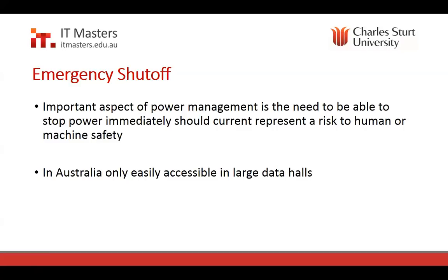So if you ever are going to hit it, don't hit it accidentally, like an old boss of mine did, wheeling in a trolley full of equipment, and he accidentally bumped into the emergency shut off for the data hall. So that was a good start to his day. What a disaster. Yes, he was actually a field tech for Honeywell at the time, and he got called out to one of the Telstra data centres in Melbourne and shut one of the floors off. By bringing a trolley full of Honeywell equipment in that he was supposed to be replacing. I mean, it was his fault. He's a bit careless, but the power shut off button wasn't adequately protected, and it wasn't in a great spot. So yeah, he didn't have a great day that day.